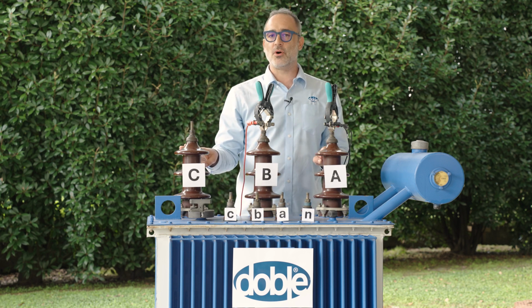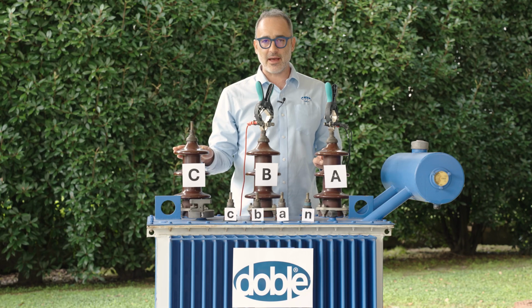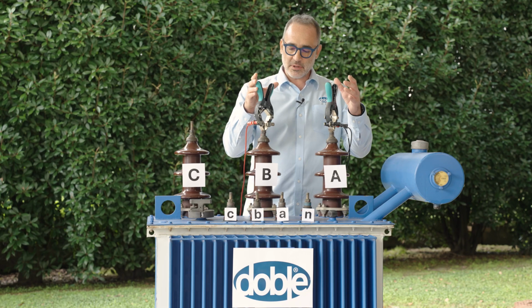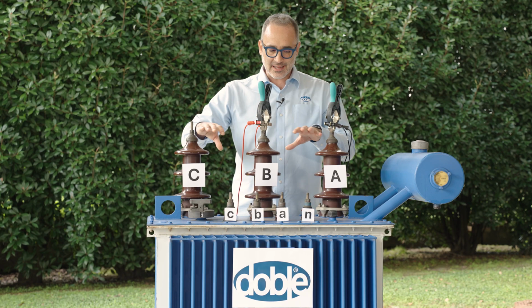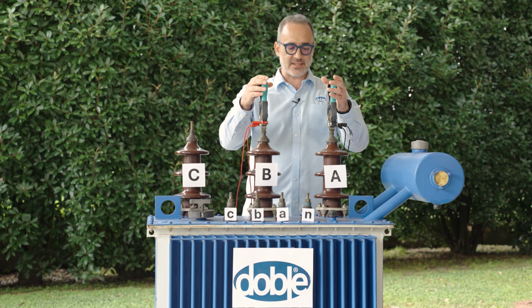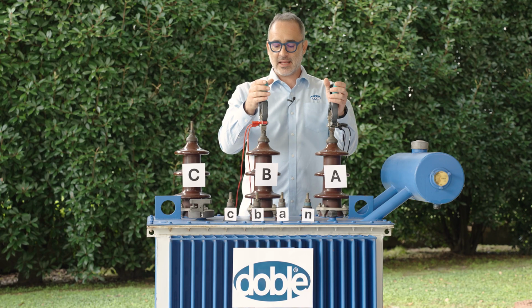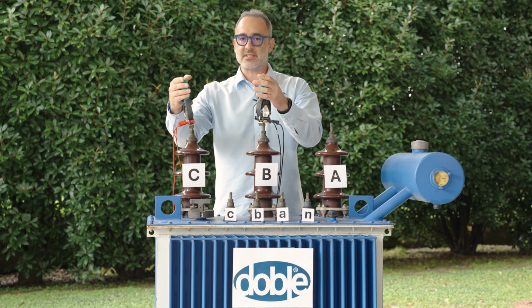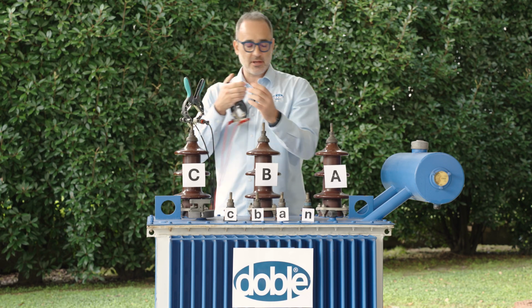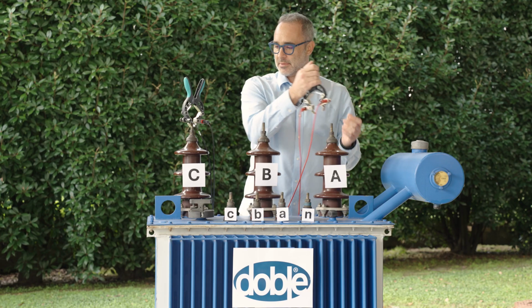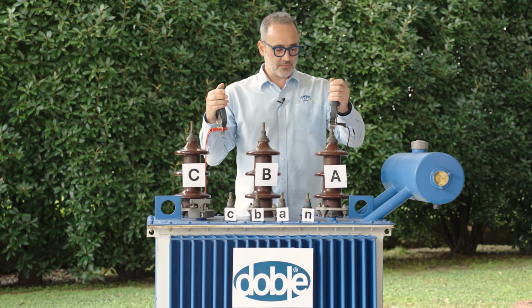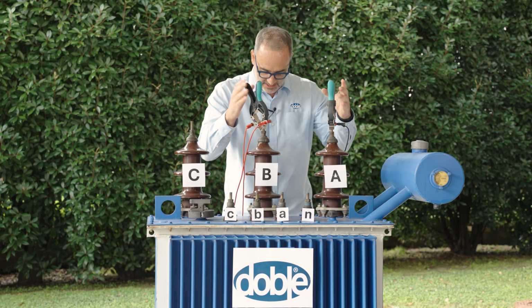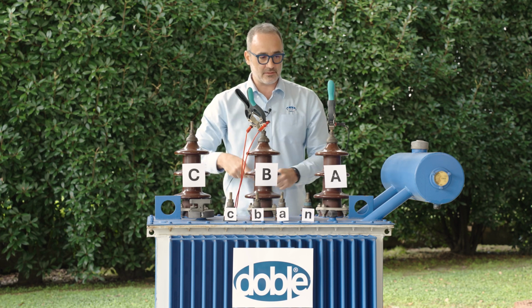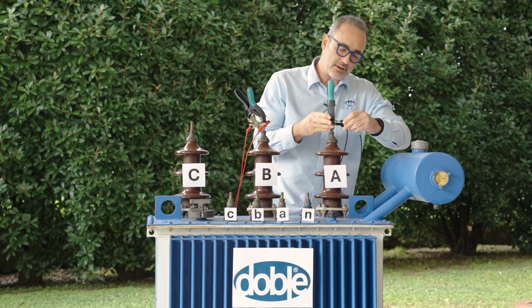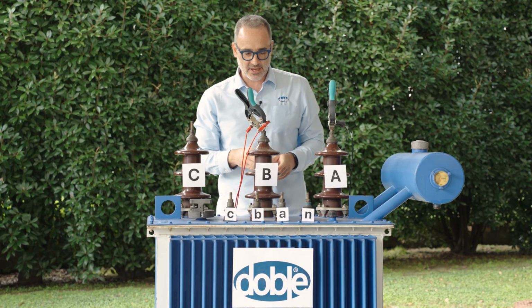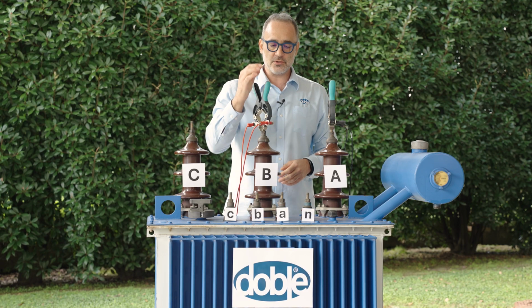For that reason, we will also change the testing current. It will not be 5 amps, it will be lower, but this would be my first measurement. Because this is a delta, first I'm measuring between phases A and B, then after that between phases B and C, and in the end between phases A and C. But now we start with phases A and B. And now let me move to the STS in order to do the test.